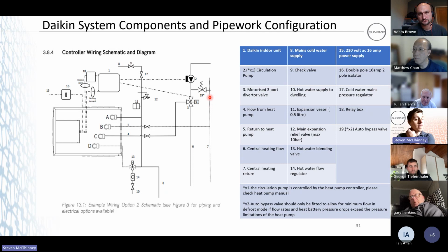I mean, the amount of times I've been to a job and that auto bypass has been fully open, it's ridiculous. So the heat pump gets up to temperature, starts short cycling, and no heat starts going to your battery. So it's all about commissioning and stuff.